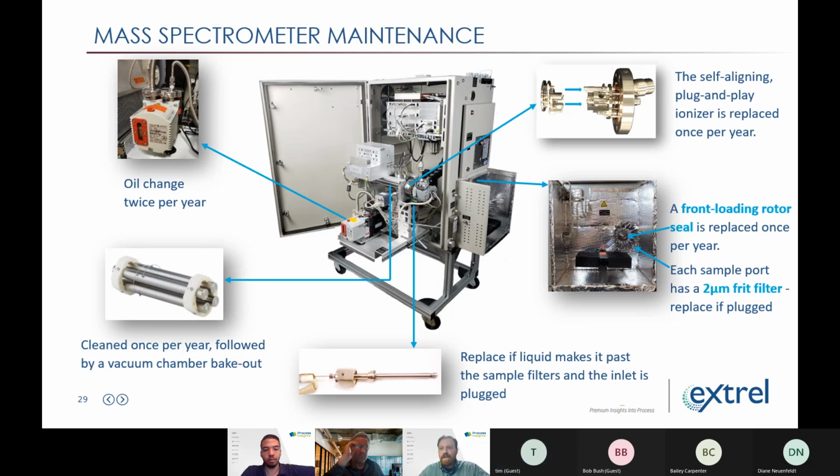One of the reasons we like to advocate that people send their staff to Pittsburgh for training as opposed to doing on-site training classes is that it's a compliance device. So you really don't want to take it offline and rip it apart. Whereas if they come to Pittsburgh, we have a couple of analyzers that are just trainers, and so they can take it completely apart, see everything, and do that a couple times.